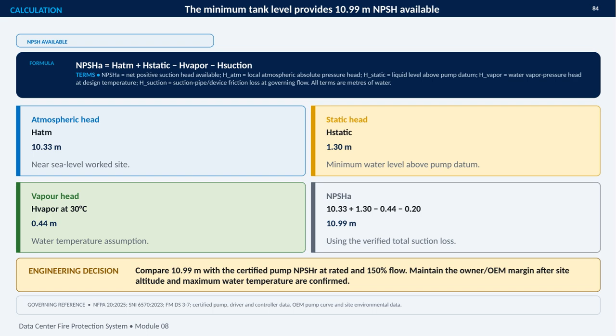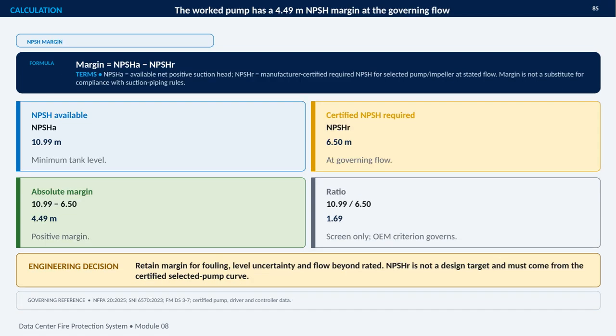Before final confirmation, the site altitude and maximum water temperature also need to be verified. The governing references include NFPA 20, SNI 6570, FM Data Sheet 3-7, and the certified pump, driver, controller, and OEM curve data. This slide checks the pump's net positive suction head margin at the governing flow.